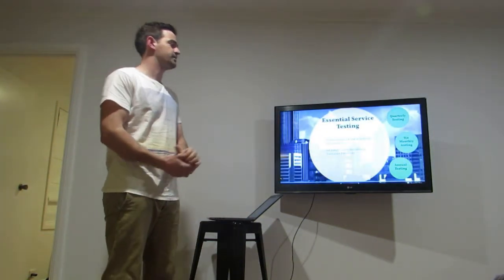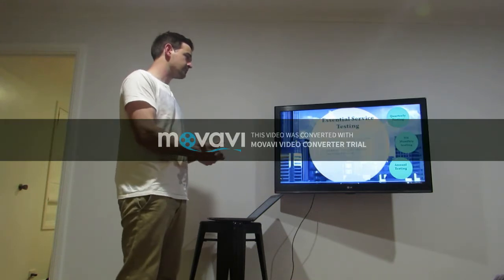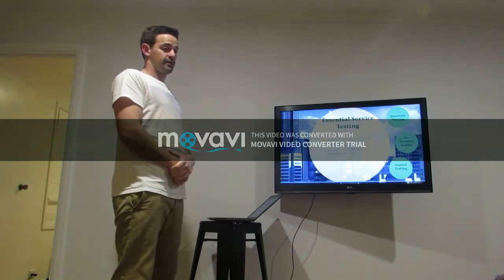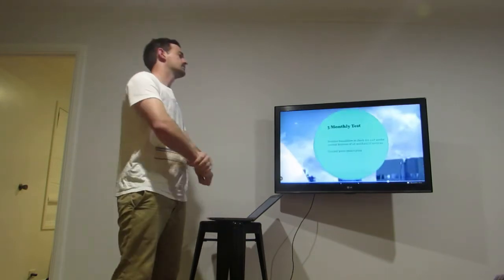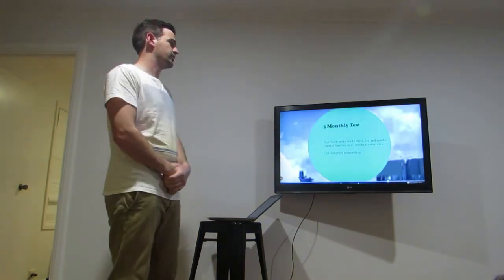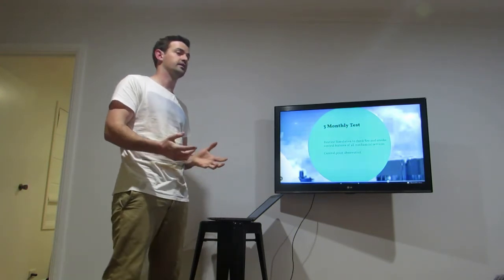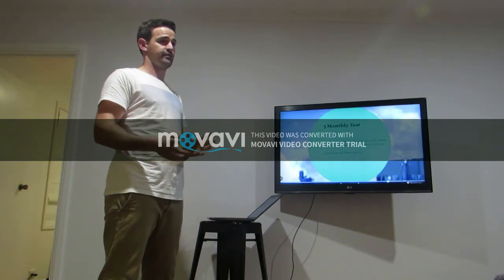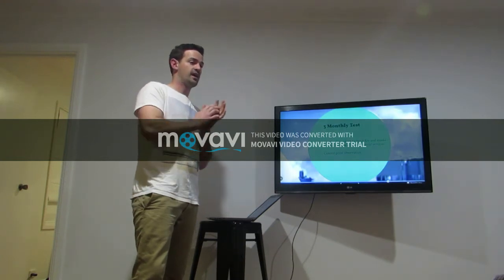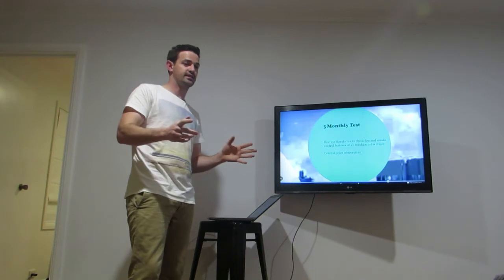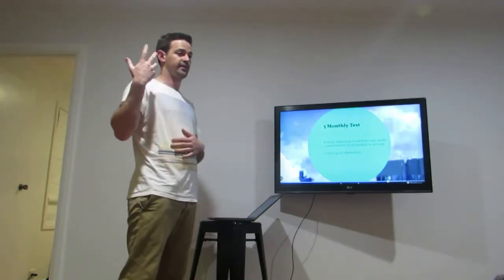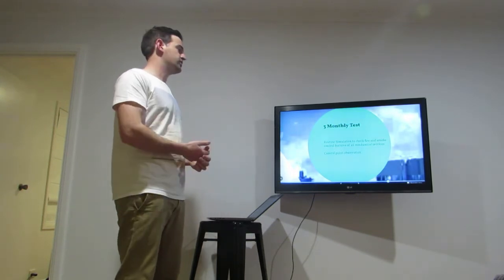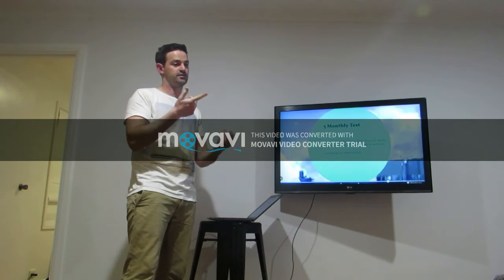Essential service testing is broken up into 3, 6 and 12 monthly requirements. All tests and tables are carried out to Australian standards. Quarterly testing is a routine simulation. This is to check that the smoke control features of mechanical services have changed over. We don't actually have to check every asset for mechanical service. We just need to make sure that the fire control panel is engaging the fire alarm and sending it out to the mechanical equipment. Fans need to start, airflows need to change. We need to check that the stairwell fans operate and smoke spill fans operate. We can use a control point observation for this. So we can use BMS, fire indication panels, streamers, and obviously our sensors.